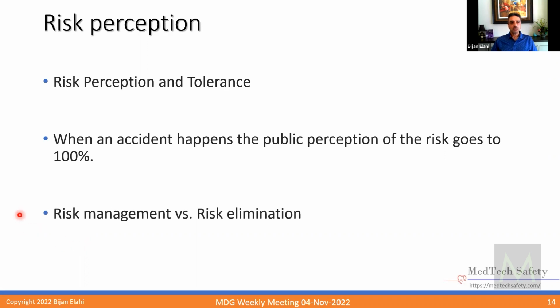Another topic I would like to mention is the difference between risk management and risk elimination. In the medical device industry, we do risk management. In other words, we recognize that risk is non-zero. There are no medical devices with zero risk. Risk elimination is about bringing risk down to zero, which practically is not possible. Risk elimination is one method of risk control, making a device safe by design or manufacture. It is a precursor to risk management. In some other industries, they just focus on risk elimination, but in the medical device industry, we actually measure and manage risk.